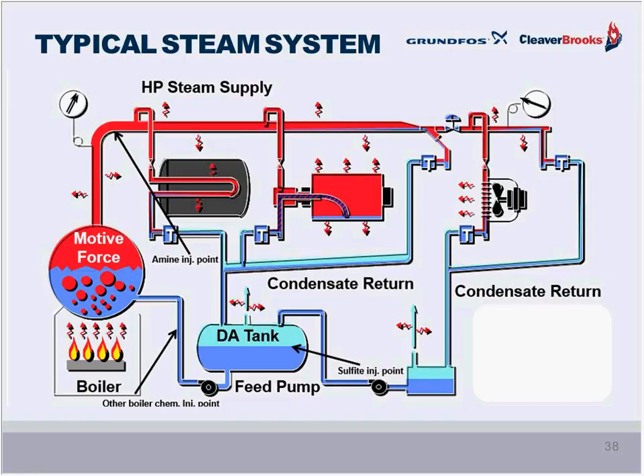You'll see the sulfite injection into the deaerator tank. A mechanical pump rated for lower pressure is used, since the deaerator tank will normally impart up to 10 psi of back pressure on the pump. This can be a problem in these systems, since dosing pumps require some minimum level of back pressure in order to dose accurately. Metering pumps will require something like 25 psi. So what we usually see is a back pressure valve set to that level, and those things are actually absolutely necessary. Otherwise, the pump cannot dose accurately. The benefits of water treatment will be reduced through the treatment of that expensive system. So we've got to balance that there.